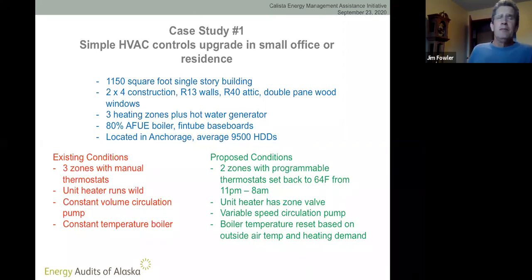So this building has 3 zones, manual thermostats, and a unit heater that runs wild. What that means is that the glycol, or the heating fluid, is running through the unit heater all the time. It has a constant volume circulation pump, which means that anytime there's a call for heat, the pump turns on. And it has a constant temperature boiler, which means that the temperature of the boiler is always at 180 degrees or whatever the set point is.